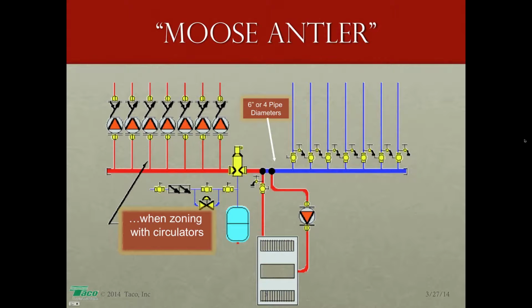And people call this primary secondary, but it's kind of a variation on primary secondary, because the primary loop with a cast iron boiler starts in the supply port of the boiler, does a loop-de-loop, and returns back to the return port on the boiler. So it's a direct supply to return loop-de-loop. And then your secondaries come off of that.